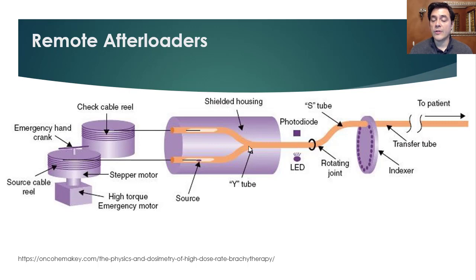And then there's a large shielded housing. And in the shielded housing, the source and the check cable or the dummy or the simulator exist at the same point. Then the stepper motor is attached to both of these, and the stepper motor is very precisely encoded, or the voltage is known so that you know what the distance is based on how many volts this meter attached to this motor reads. And then for all emergencies, there's an emergency hand crank. So there are many redundant systems for the emergencies that potentially could occur. The emergency hand crank is sort of the last stop.